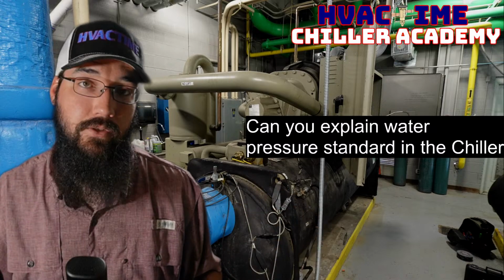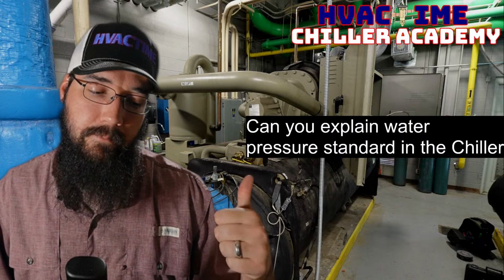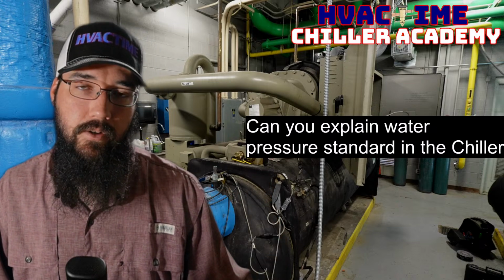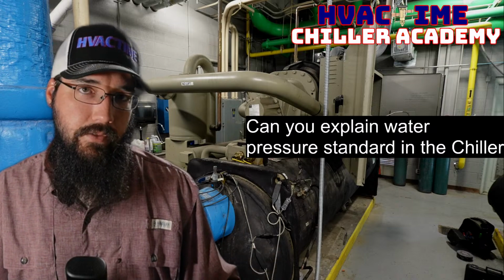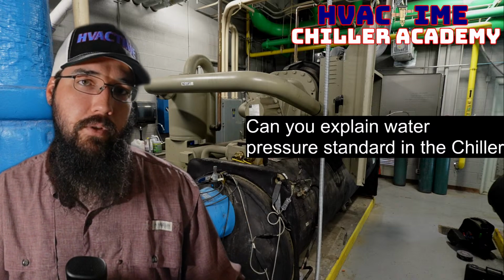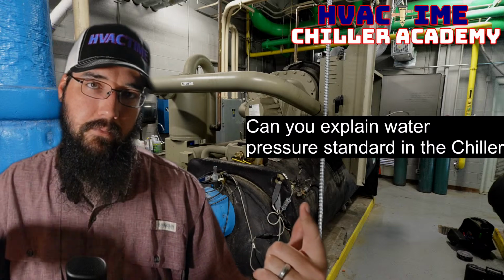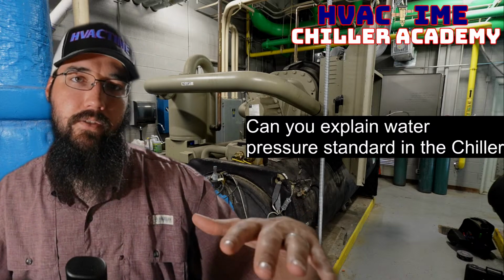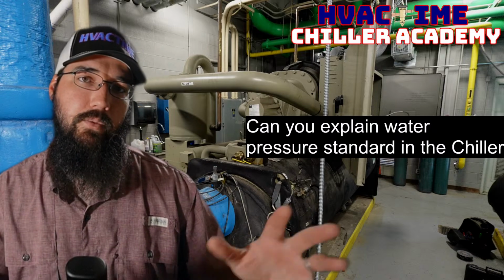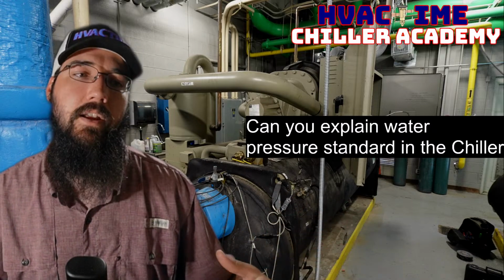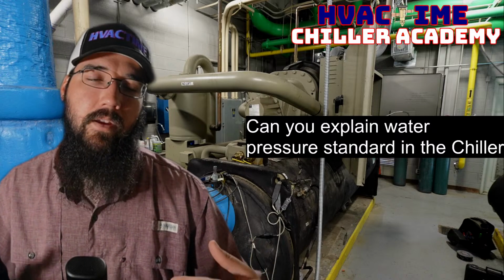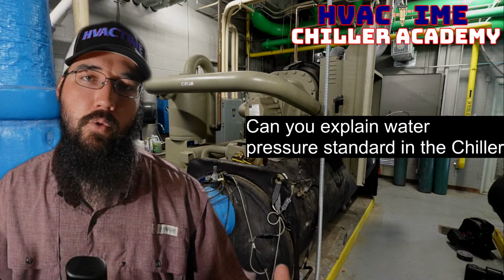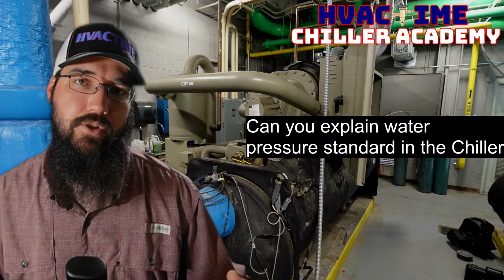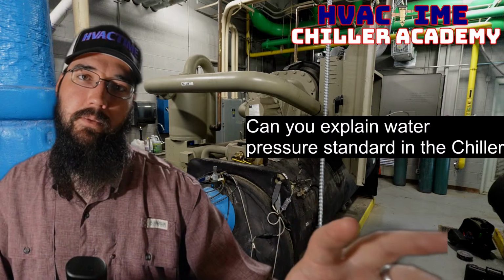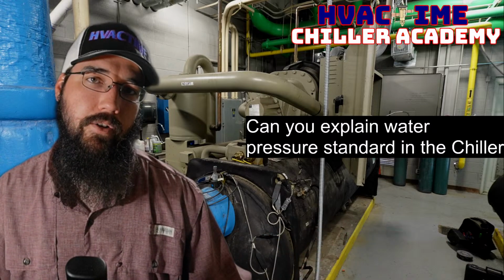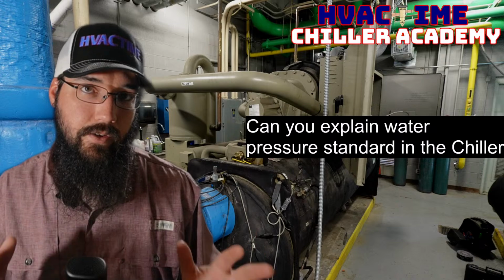And this is true for condenser water. This is true for chill water. One of the things you have to caveat here is, if you have an open loop tower on the roof, but several stories down, the open loop tower does change things a little bit, because we have an open loop system. We can't pressurize it the same way we can with pipes. But because it's open loop, we don't have those same cavitation issues. Things change a little bit because there is some give and play without forcing the water into a cavitation state with an open loop system.